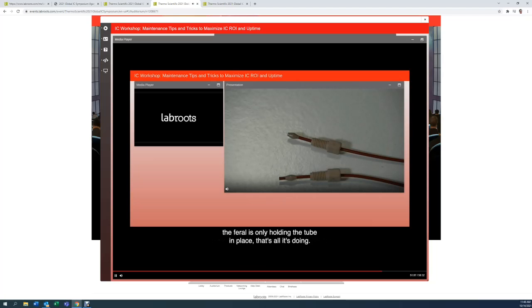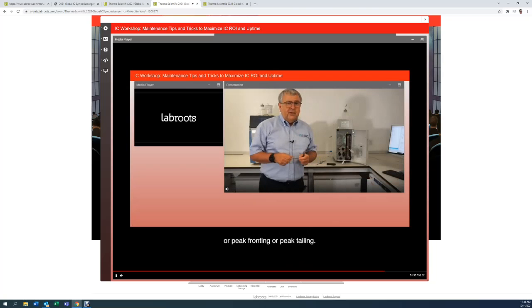That's all it's doing. If we don't do it that way and the ferrule slips forward on the piece of tubing, what will happen is it'll be the ferrule which is in the column, and that is going to cause dead volume or a disturbance, and that's going to cause you band broadening or peak fronting or peak tailing.